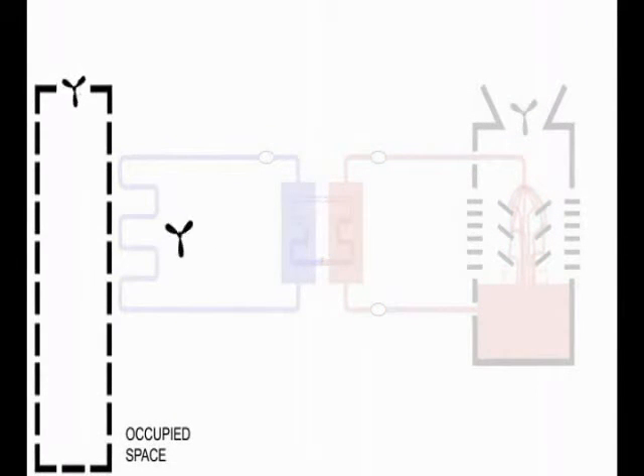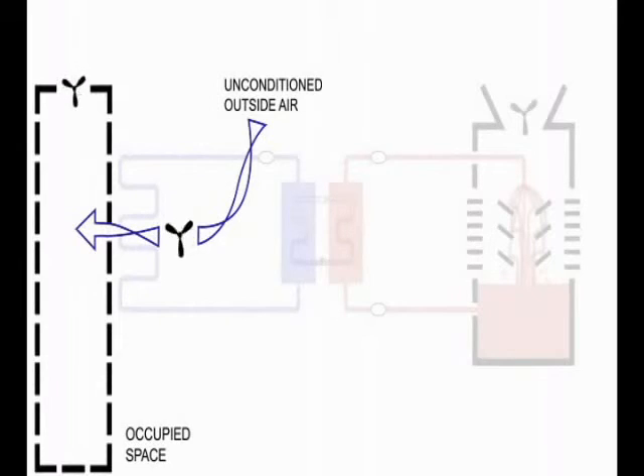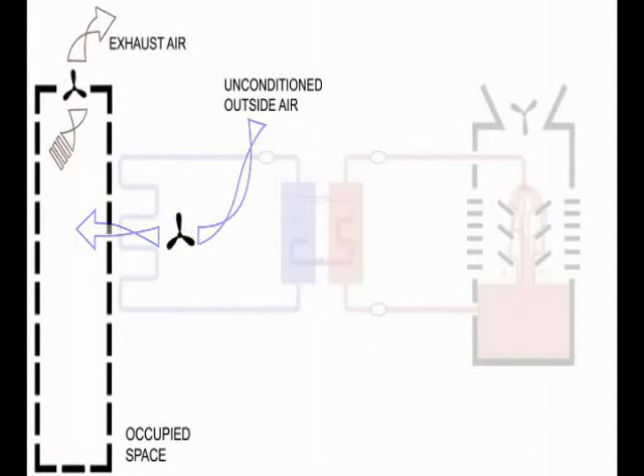In this case, in the air side economizer, it may be more energy efficient to directly introduce cold outdoor air to the inside so your equipment doesn't have to mechanically cool the warmer recirculated air. As a side benefit, this offers superior indoor air quality. All that fresh air replaces what would otherwise be mostly recirculated air.